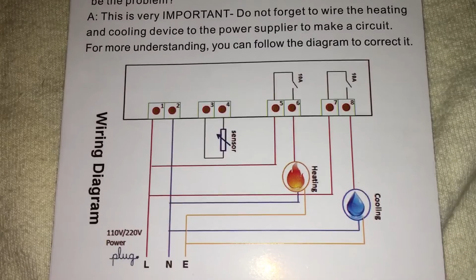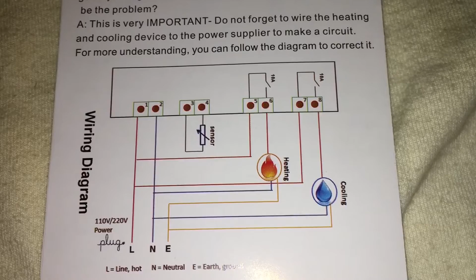Okay, so that's that. 10 amps on your relay contacts again. There's your sensor - line and neutral are 1 and 2. 3 and 4 is your sensor. 7 and 8 is a set of contacts. So you've got that.